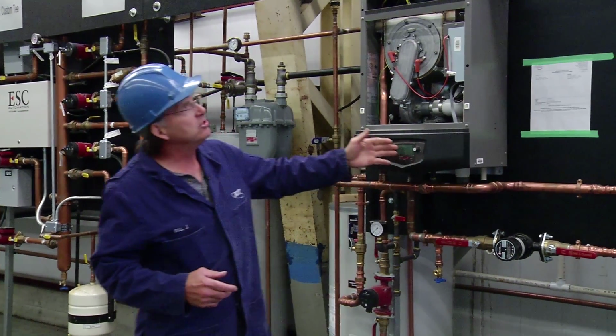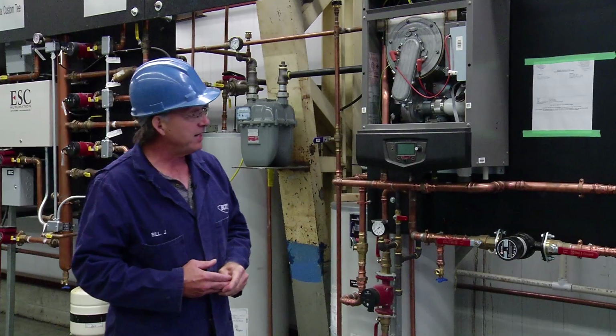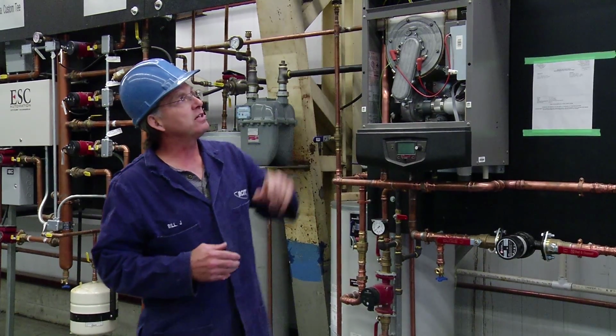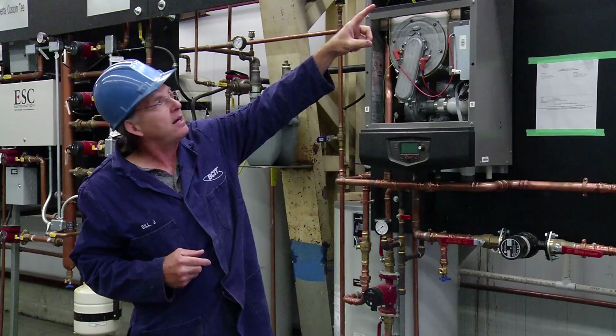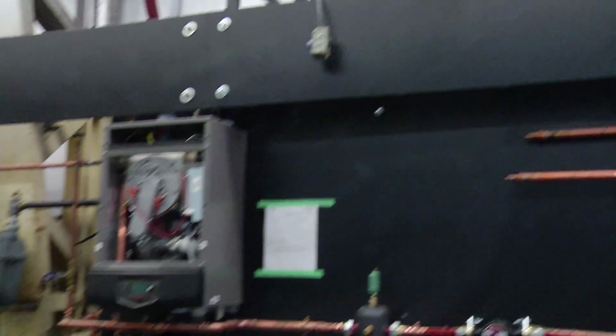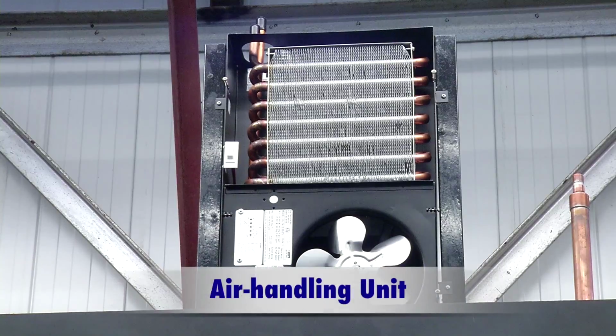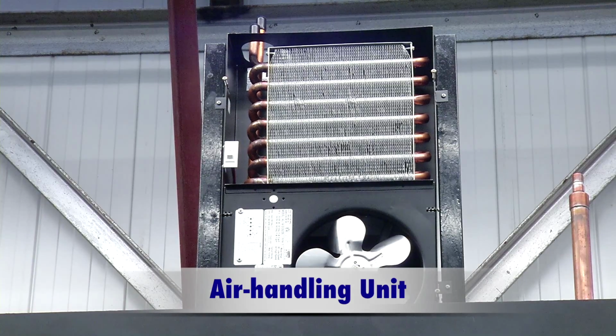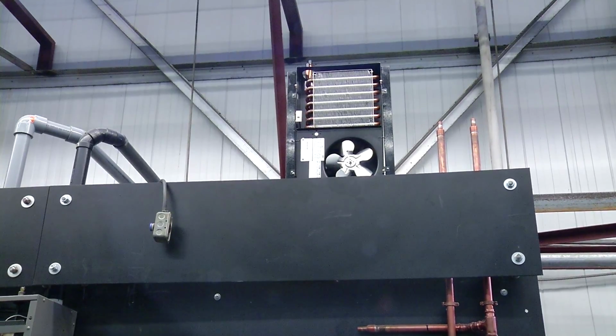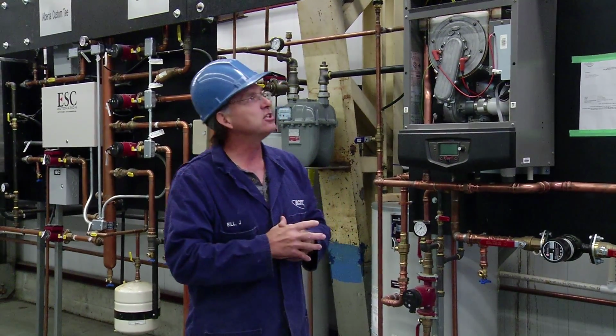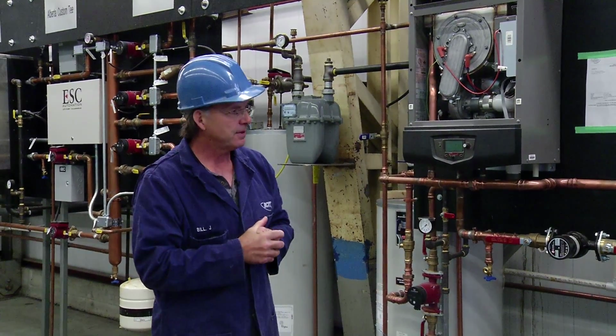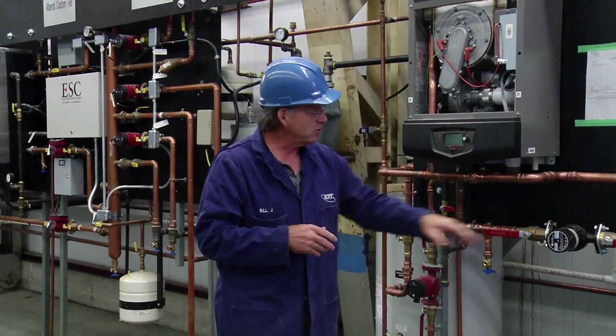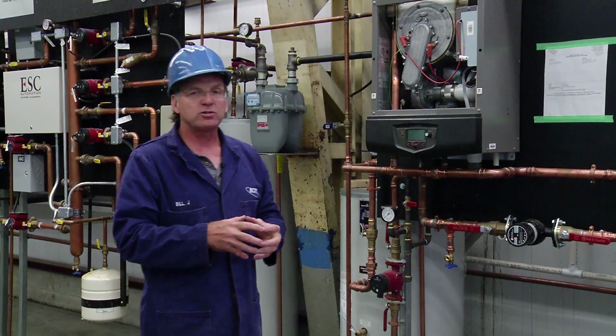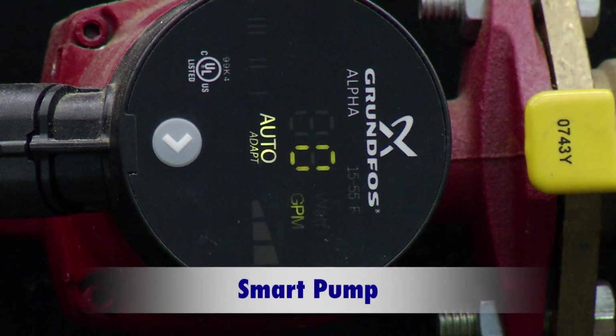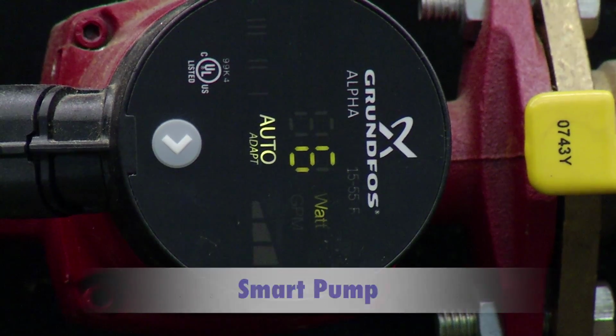Another thing that we can do in terms of the flexibility of hydronic heating is to look at different heat emitters. If we pan up top there, there's an air handling unit. It's a very small one for the residential, but here we'll put hot water to that, and then we'll drive heat through a heat exchanger, and we'll be able to heat up some air for any additional heat that we might require. This particular system also features the smart pumps that we can change in terms of how fast they go based on how much demand we need from them.